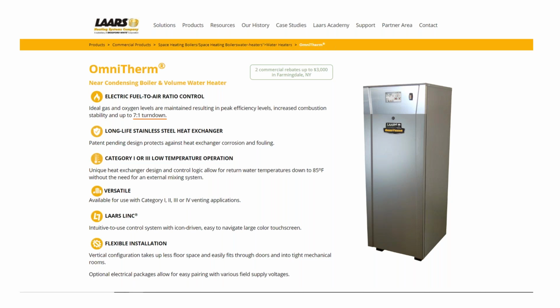It has a 7-to-1 turn down because it has a new oxygen gas train sensor and valve control system built in. Super long life stainless steel heat exchanger built in. It can be category 1 or 3 for low temperature operation. And it's versatile. It can also be 1 through 4 basically as well. But the 7-to-1 does come in at the 2 and 4 category ratings. Laars Linc is integrated into this, and we'll get into Laars Linc in a little bit. And there's flexible installation. It's a small footprint. It'll fit into most elevators. I have to say that. And it's a very good overall package design. Very nice, neat, and tidy.